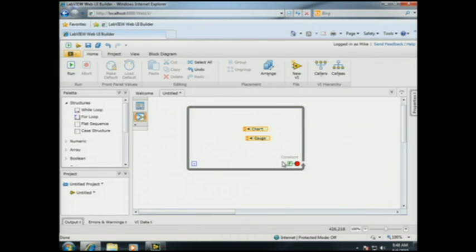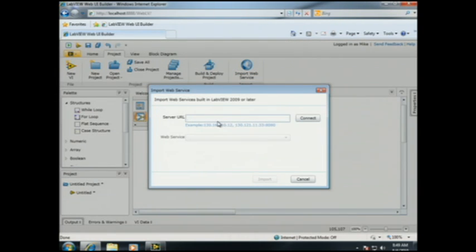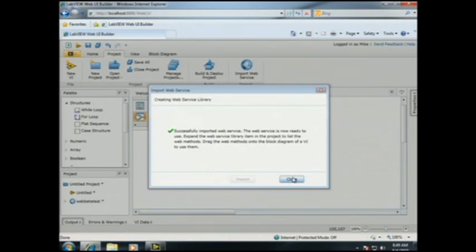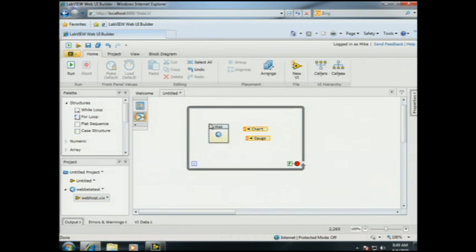The final piece of our demo is communication with the remote CompactRIO system. For that we use the Import Web Service Wizard. We give it the address of the device we wish to communicate with, and once we connect, it gives us a list of all the web services available on that target. We pick the one we want and import it. What this does behind the scenes is script functions and add them as sub-VIs to our project automatically. We can then simply drag the sub-VI onto our block diagram and wire it up to those indicators we dropped earlier on our panel.